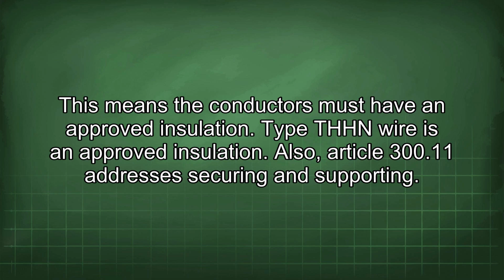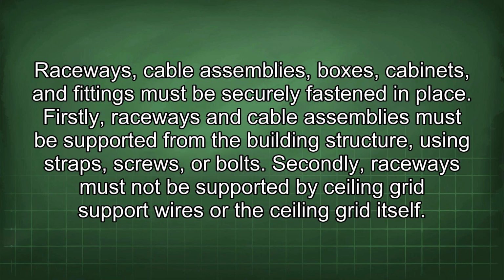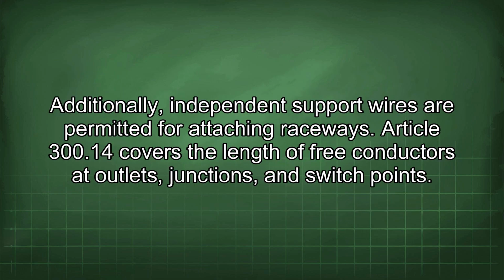Also, Article 300.11 addresses securing and supporting. Raceways, cable assemblies, boxes, cabinets, and fittings must be securely fastened in place. Firstly, raceways and cable assemblies must be supported from the building structure using straps, screws, or bolts. Secondly, raceways must not be supported by ceiling grid support wires or the ceiling grid itself. Additionally, independent support wires are permitted for attaching raceways.